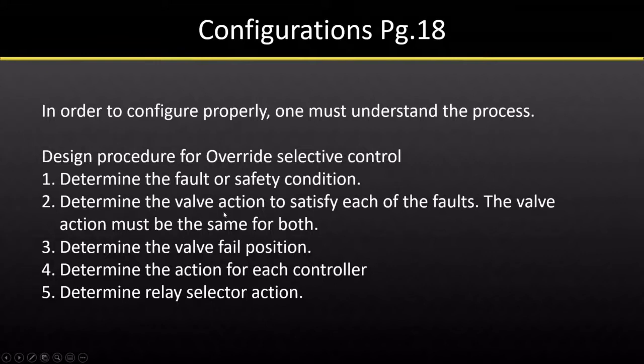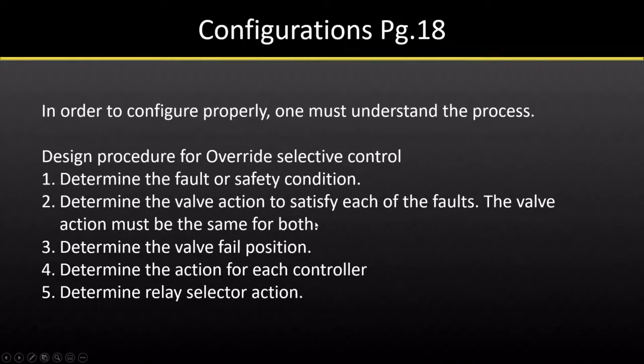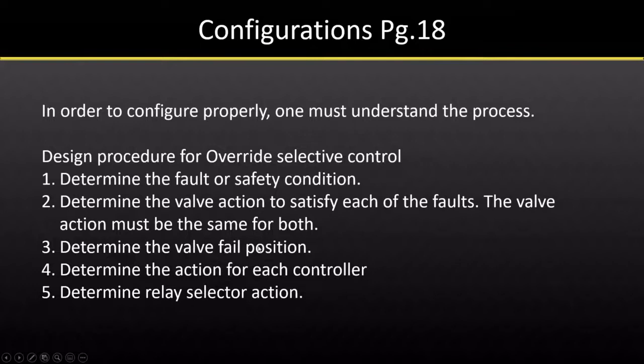Then determine the valve action to satisfy each fault — if you get high pressure, do you open or close the valve? Once you identify your conditions, identify the safety action — it has to be the same for both, because there's only one way the valve can fail. Then determine the valve fail position, then determine the action for each controller (direct acting or reverse acting), and finally determine the relay selector.